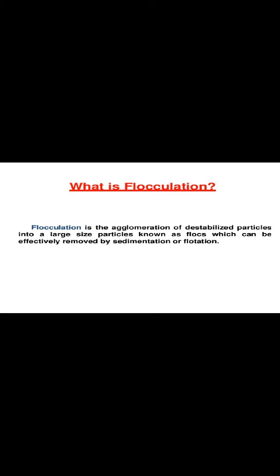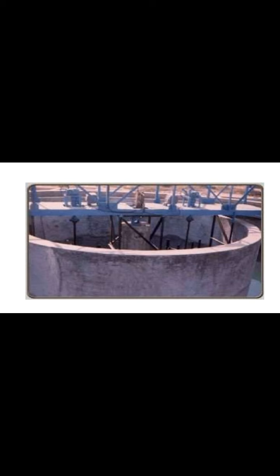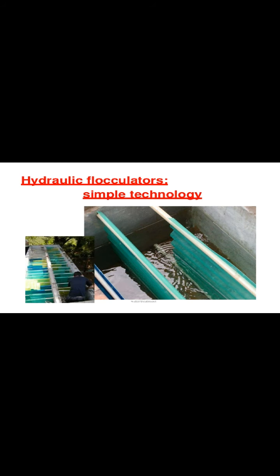Flocculation is generally the agglomeration of destabilized particles into large size particles known as flocs, which can be removed by sedimentation or flotation. Mechanical flocculators are used, including cross-flow flocculator sections. Hydraulic flocculators are also provided in water treatment plants — horizontal baffle tanks where water flows horizontally, with baffle walls creating turbulence to facilitate proper mixing.